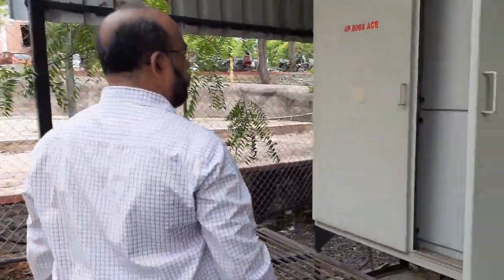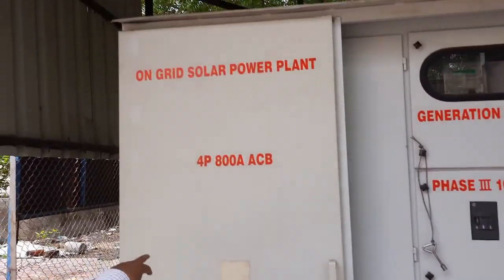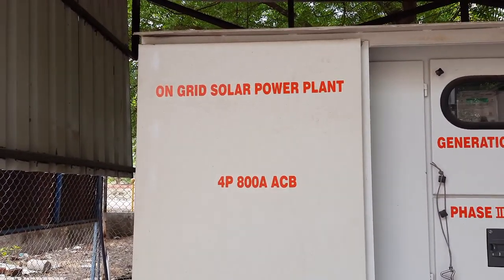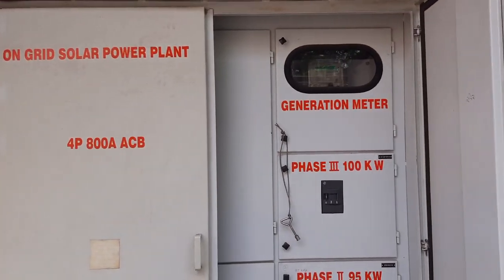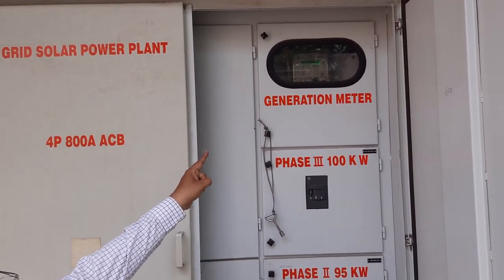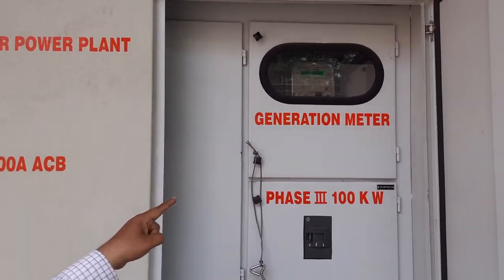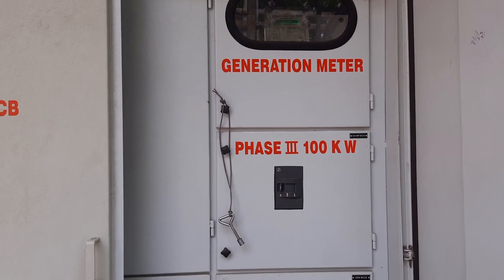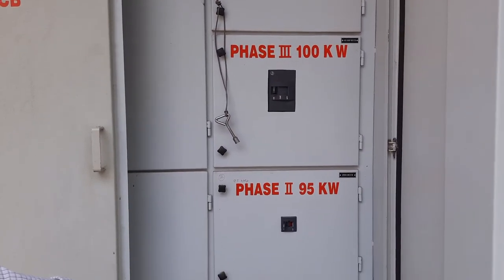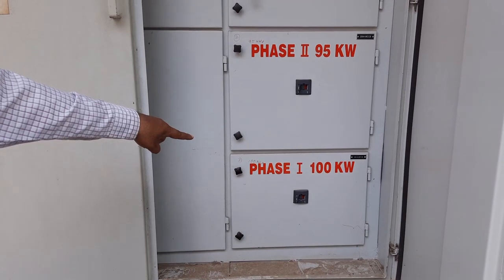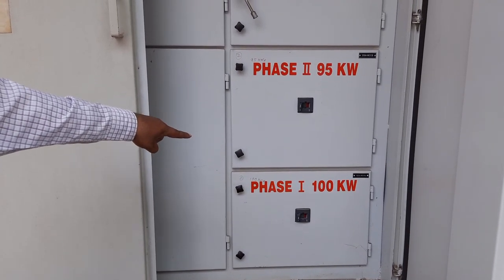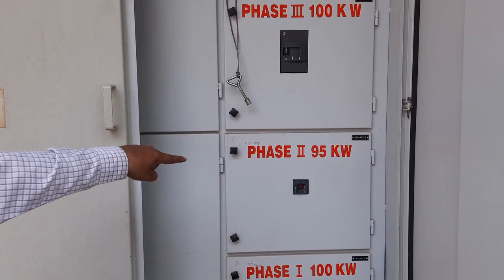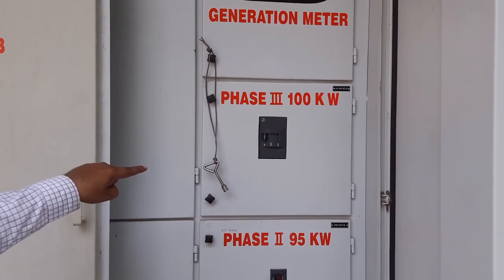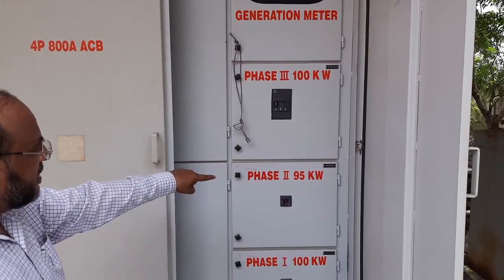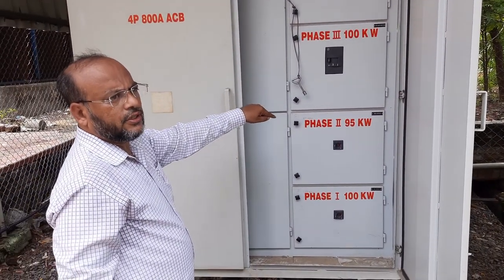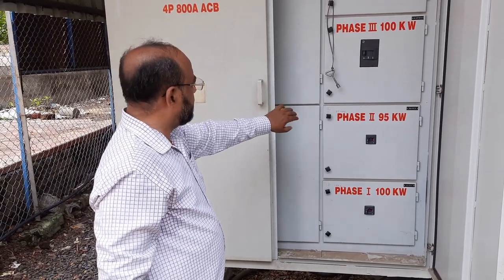This is the solar generation panel, for the on-grid solar power plant. It has a 4-pole 800 ampere ACB. It comprises a generation meter, which measures the electricity generated by the solar plant in our campus. And these are the three phases of the solar plant. Phase 1 is 100 kilowatt, installed in March 2018. The next was in August 2019, and again March 2020. So this is 100 plus 95 plus 100, a 295 kilowatt solar power plant in our campus.